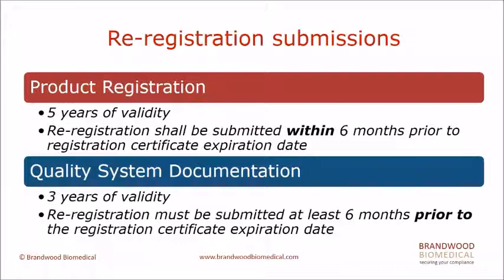The second re-registration submission is for the quality system documentation. The QSD certificate is valid for 3 years, and the re-registration must be submitted 6 months before the certificate expires. According to the regulation, without a valid QSD certificate, the devices are not allowed to be legally supplied in Taiwan. So it is important to ensure that all certificate renewal applications are submitted within the timeline to be able to continue supplying the products in Taiwan.